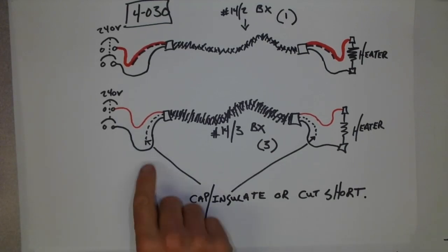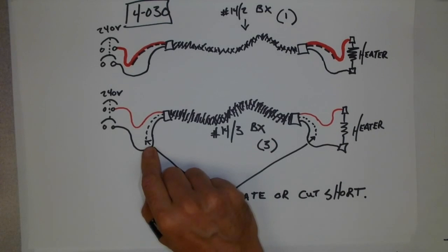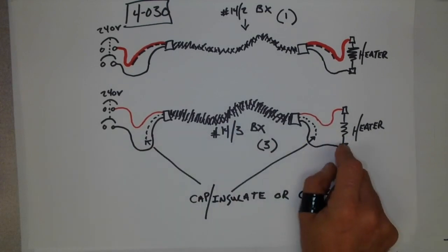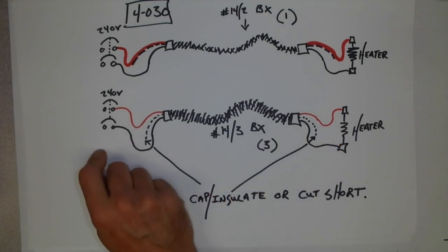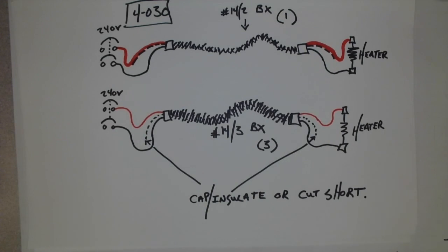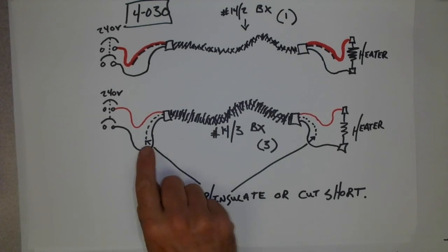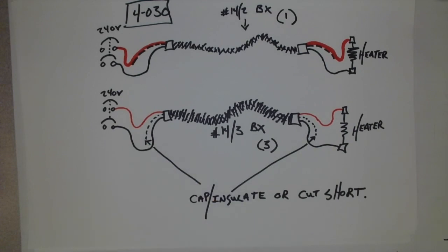When you come to a panel board and you see a wire that's just sort of dangling about and something's wrong with the heater, some people's first impression is, oh, well, that wire came off. I better fix it to the neutral bar. And this can introduce problems. So if the conductor is not being used, you have to insulate it, cap it, or cut it off short. So I hope that gives you a little bit of clarity on how we utilize identified conductors with cables in the 2018 Canadian Electrical Code and going forward from it.